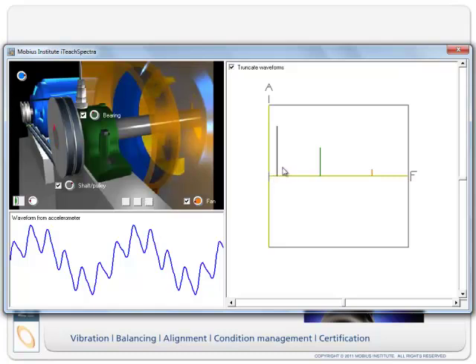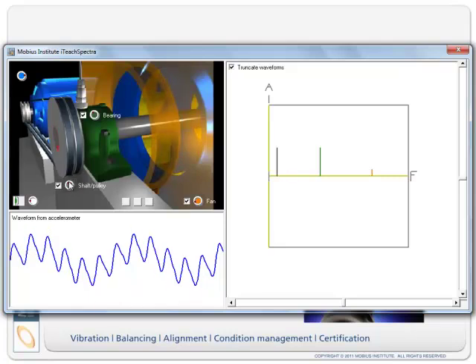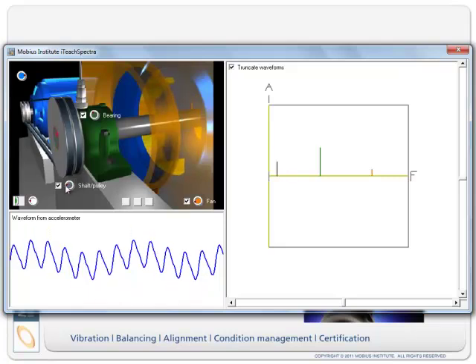And the last step of the rotation will actually chop off the bottom. And there is our spectrum. We have one peak here that relates to the once per revolution vibration, which could be unbalanced, could be bent shaft. It could be a couple of things, eccentricity and so on. But keeping it simple, we'll just talk about unbalanced. And if we don't have very much vibration at that frequency, if it's really running quite smooth, it's been balanced well, then that peak will be lower. And you can see how much easier it is to look at this than this here.